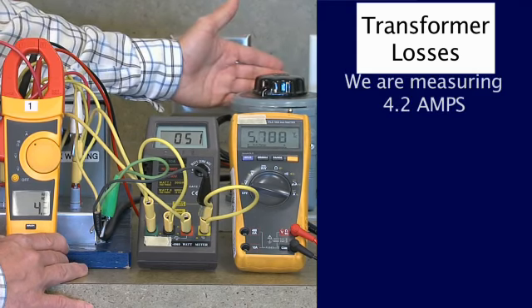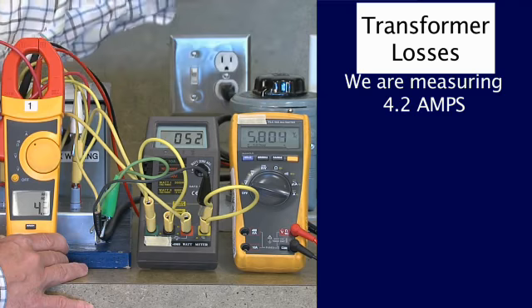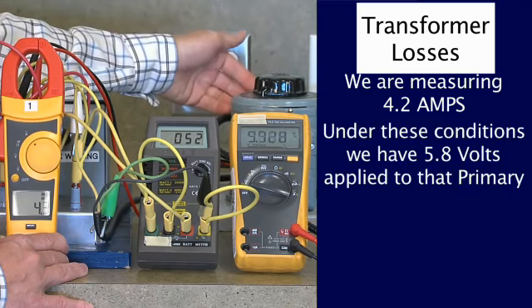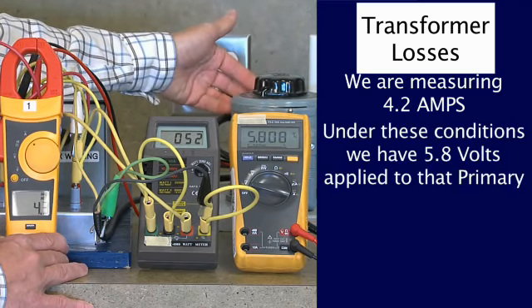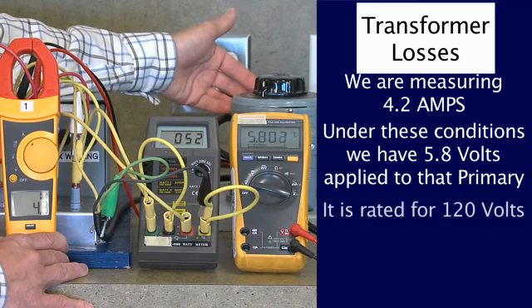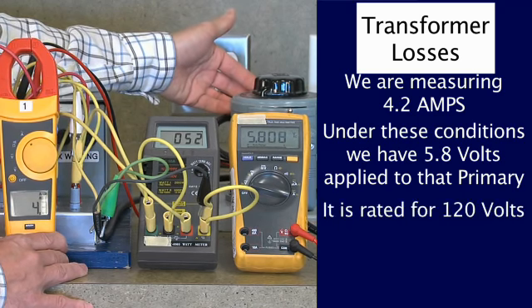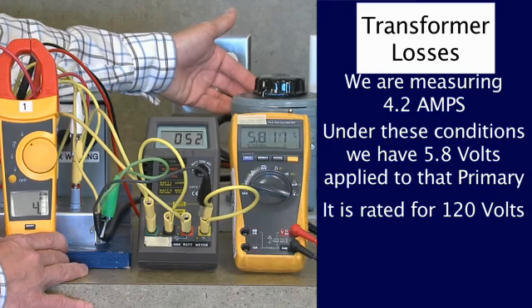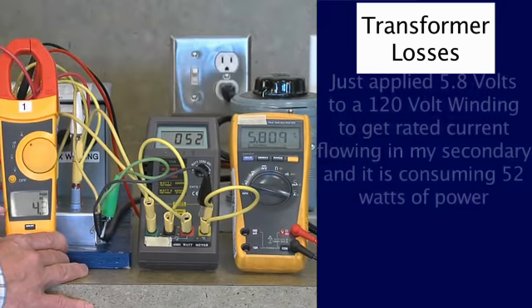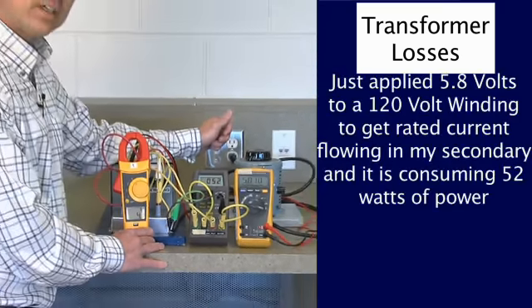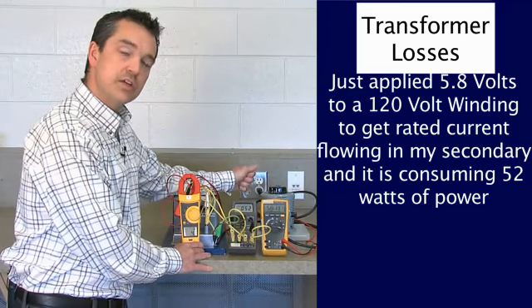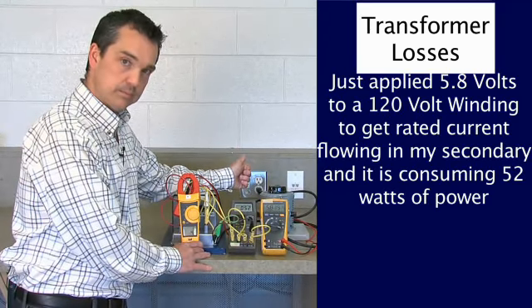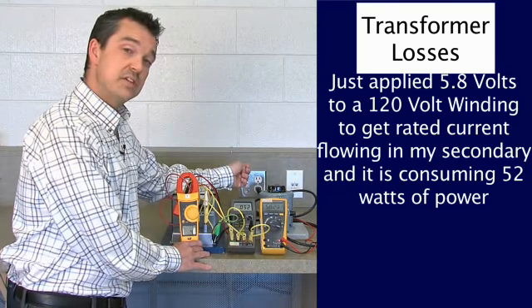Under those conditions, you can see the voltage is only about 5.8 volts applied to that primary. Remember, it's rated for 120. So I've just applied 5.8 volts to 120 volt winding to get rated current flowing in my secondary. And it's consuming 52 watts of power. What is this test good for then?